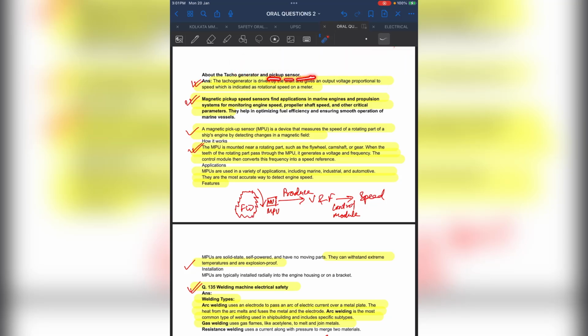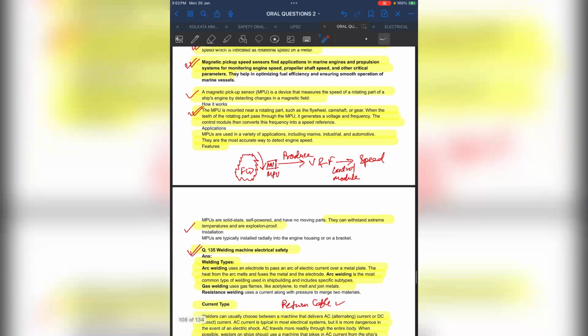And there is a pickup sensor, which is a magnetic pickup sensor type, and it is fitted near the flywheel. Suppose your ship propulsion flywheel is there, and there is an MPU, a magnetic pickup sensor unit, fitted near the flywheel. The magnetic pickup sensor is connected with a supply, so there is a magnetic field, and whenever the flywheel rotates, due to the teeth dimensions this magnetic field and flux change, and due to this change in flux a voltage and frequency are produced.